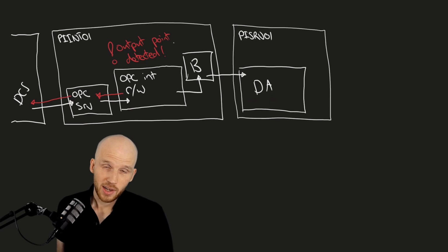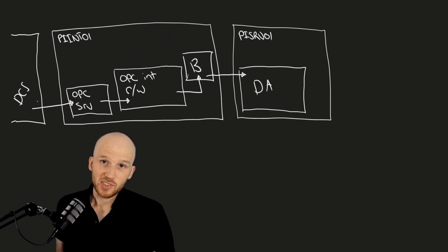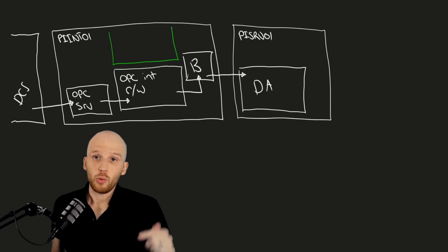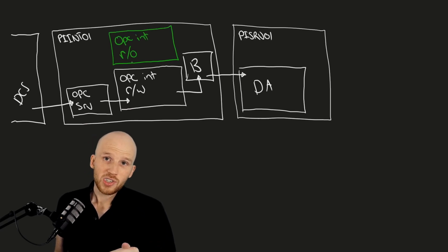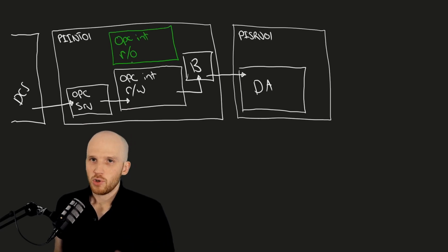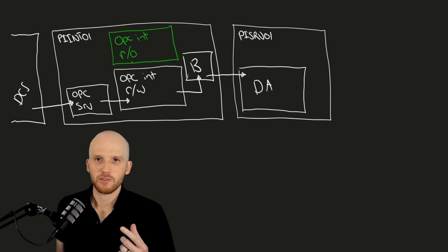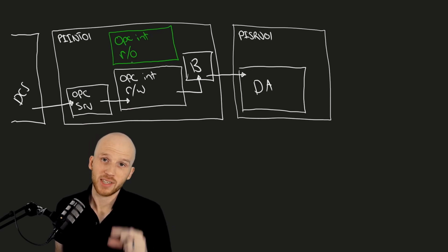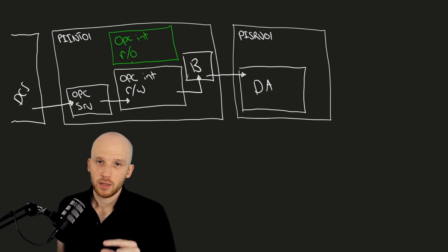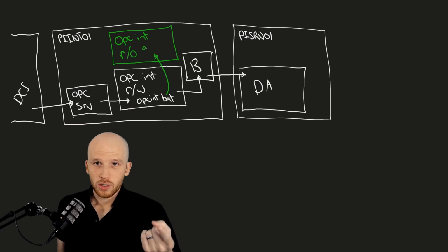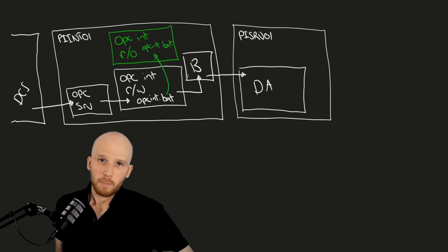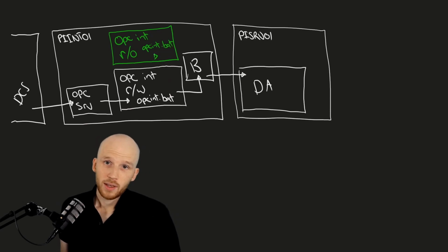So in this class, we're fixing up a poorly implemented system. We're going to install the read-only version of the interface. This version is effectively the same as the read-write version, but it doesn't have any functionality relating to writing back to the OPC server. We'll actually have two interface versions installed at the same time, a read-write and a read-only.